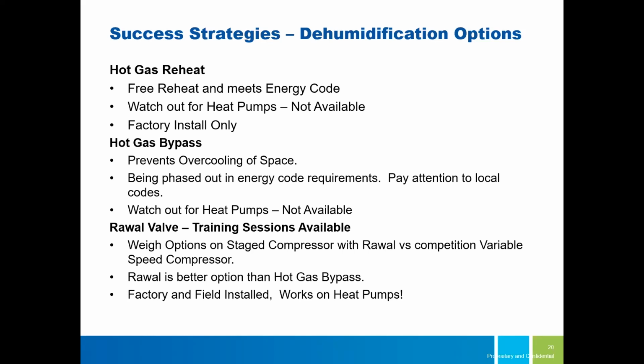Hot gas bypass prevents overcooling of the space, but it's being phased out, so you have to pay attention to your local codes. You also have to watch out for heat pumps, because it's not available there. And then you have the Rawal valve, which we have specialists who can geek out about all day, and they can do training sessions for you if you'd like. When I first heard a presentation about Rawal valves in this depth, people said, well, with a VSD compressor, why do I need a Rawal valve? I'm like, okay, well, maybe that's good.